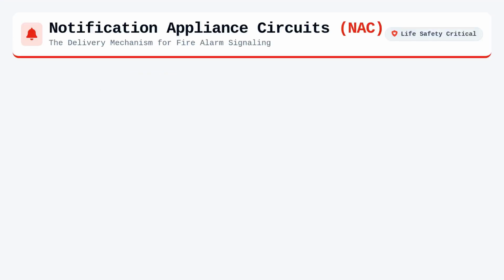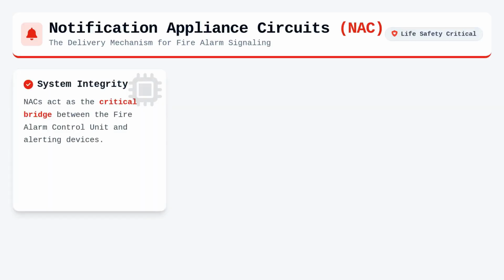Notification appliance circuits, or NACs, represent the delivery mechanism for fire alarm signaling within a structure. These circuits bridge the gap between the fire alarm control unit and the physical devices intended to alert occupants during an emergency. In a purely technical sense, an NAC is an electrical pathway monitored for integrity, meaning the system continuously checks for physical breaks or shorts that might prevent a signal from firing.